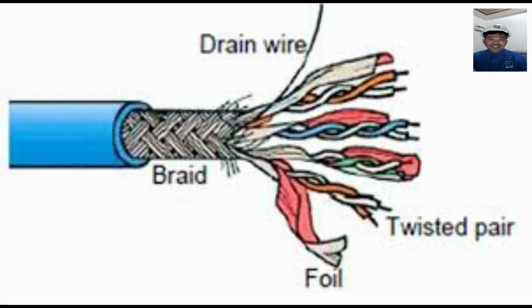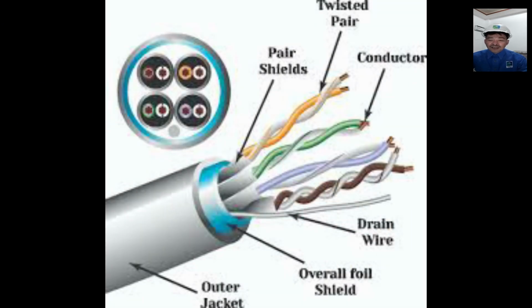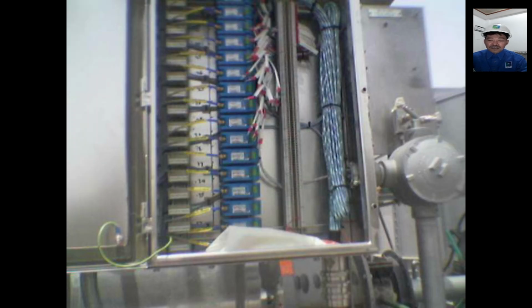So this is if you are an instrument technician, you know the termination. This is very important in termination because you're gonna find the drain wires and the mylar shields on shielded cables, and you should know what to do, and this is the requirements for that. So you don't need to terminate those wires, the drain wires. You're gonna put the cap so that it should not be touched inside the boxes, should be insulated only.